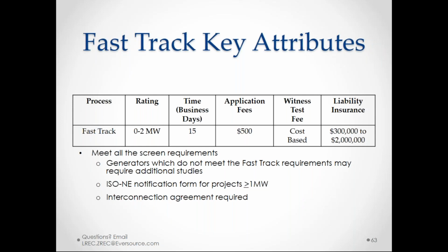On the next slide, the fast track process covers anything up to 2 megawatts; anything that didn't fall into the simplified process has the increased $500 application fee. The witness test is case-by-case. Typically, for contractors who've already had their 3 required tests, Eversource allows self-certification, agreeing to self-test the system, filling out a certificate of compliance stating the test was done and passed, signing it, and sending it back to us. That's currently available for projects 100 kW or less.